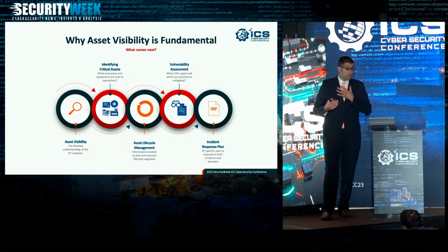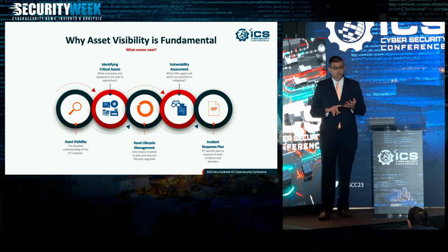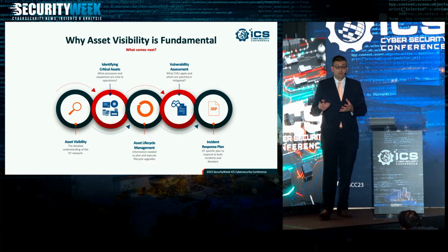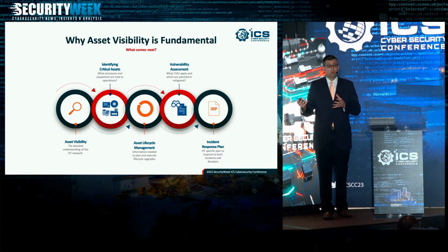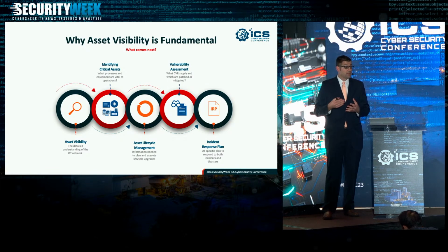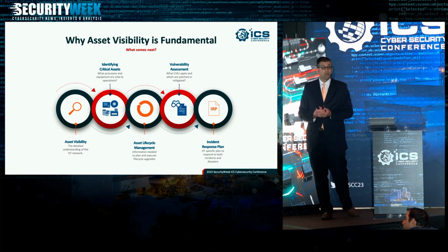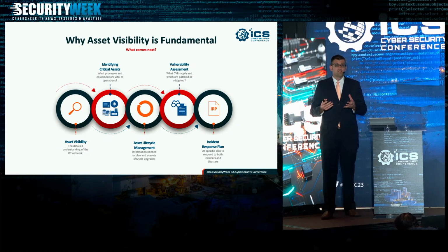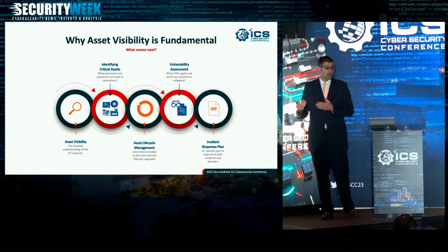Me personally, when I think critical assets, I think of the PLCs running these processes, and critical servers. But that air tank really is a critical asset, a crown jewel, because the whole process is dependent on it. So that was one of the cool things we found in a physical walkthrough. We knew, hey, let's make sure we've got redundancy in place now. Let's make sure that we never have to worry about losing an air tank and shutting down a process. So knowing the critical assets, we can start prioritizing our time and our investments to make the biggest impact.